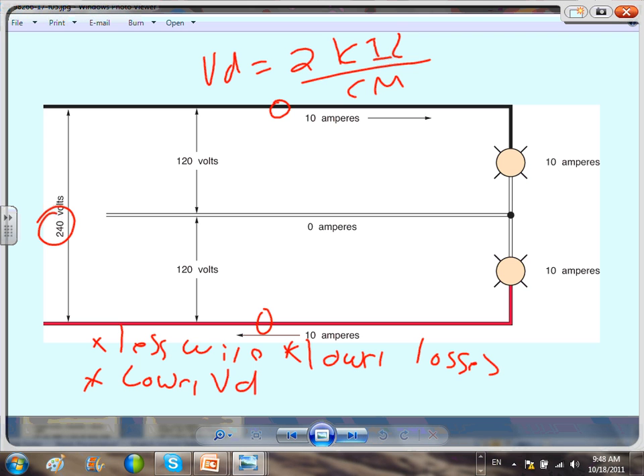Do you agree with me? Do I count the losses in this cable here? No, when they're balanced. So by counting the losses only in two cables, the neutral is not counted. It will save you also on the voltage drop. And there's an example of how the voltage drop will be less on a multi-wire branch circuit. Less voltage drop. Everybody can see, guys, a 10 amp came here, a 10 amp came here. Right at this point, they neutralize themselves to a big fat zero, right? Multi-wire branch circuit, they neutralize themselves to a big fat zero.